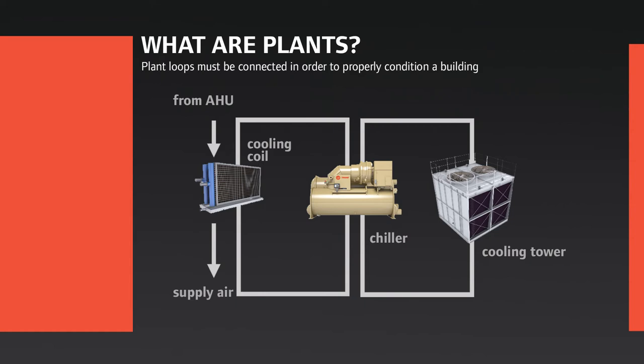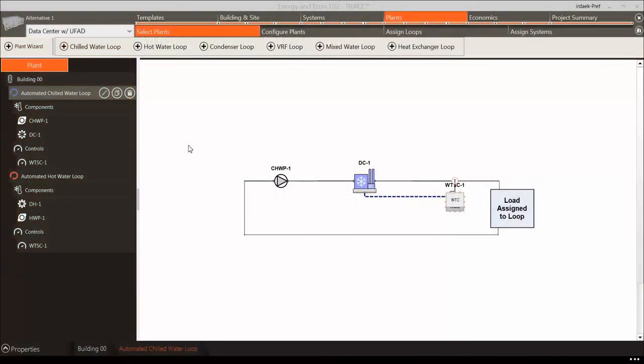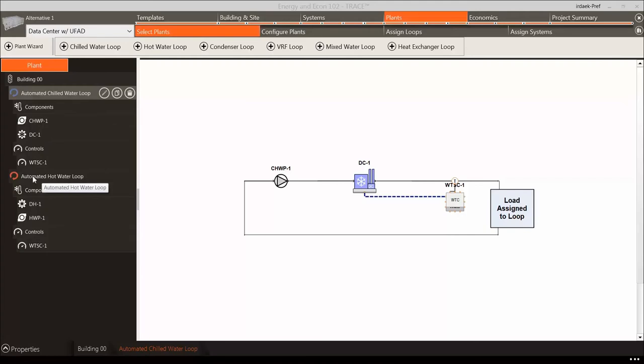Let's open TRACE 3D Plus and look at how to select plants. In the previous load design example, we used the default simple district cooling and heating automated plant. However, to run an accurate energy analysis, we need to input specific cooling and heating equipment. For our example, there will be two air-cooled chillers for the chilled water coils and a boiler for the preheat coils. We need to first delete the chilled water and hot water loops that are currently selected by navigating to Select Plants, clicking the loops in the tree, and clicking Delete.